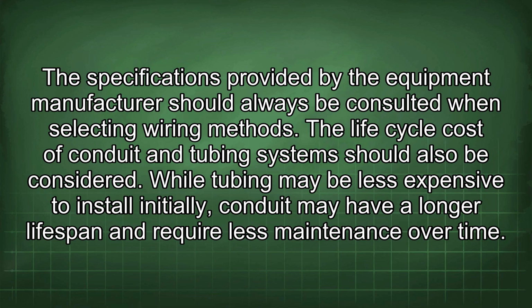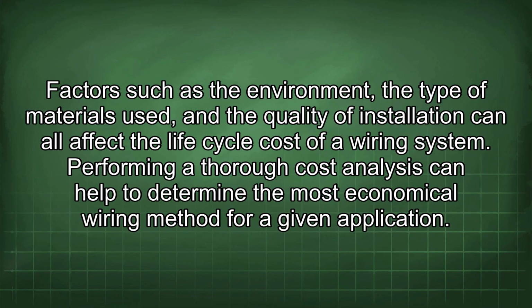The life cycle cost of conduit and tubing systems should also be considered. While tubing may be less expensive to install initially, conduit may have a longer lifespan and require less maintenance over time. Factors such as the environment, the type of materials used, and the quality of installation can all affect the life cycle cost of a wiring system. Performing a thorough cost analysis can help to determine the most economical wiring method for a given application.